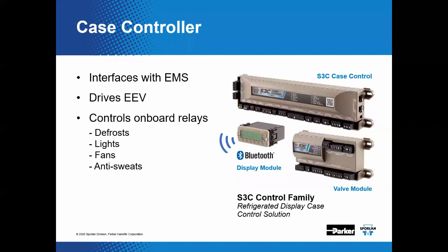Okay. All right. Well, that sounds pretty straightforward. And I'm told it can readily interface with the typical building EMS or BAS and can control many additional parameters as well. In fact, the case controller can not only drive the EEV, but it also has onboard relays to control the lights, defrost, fans, and even anti-sweat devices. These case controllers are typically in communication with that energy management system or the building automation system for data storage. And something neat here, I'm told, Glenn, it looks like the S3C itself has onboard storage for up to what? Is that right? 14 days of data. 14 days. Let me see if I do the math on that. Is that how many weeks is that? That's 2 weeks, Jim. Wow.